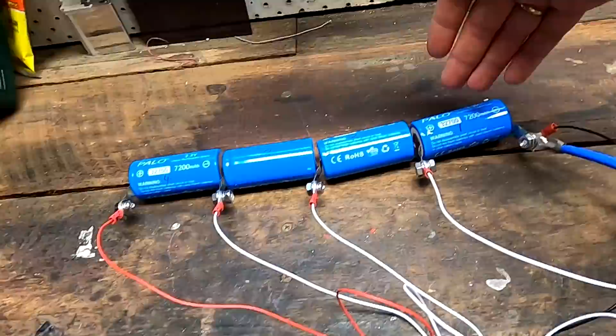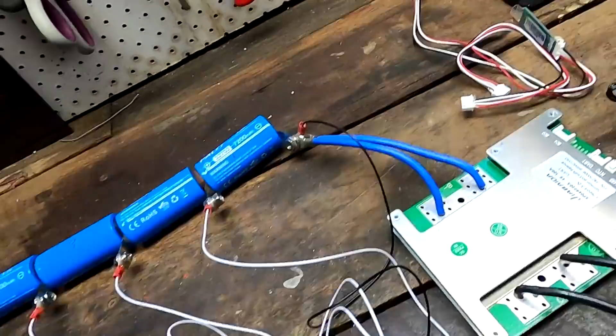In the manual, it says especially to connect the B- cable first. I'm not sure if this is a general rule for BMSs, but I usually forget to connect the B- cable and I hook in all the balance cables and then I wonder why cell number 1 is not reporting correctly. We should stick with what's in the manual, right? We don't want to have any magic smoke here on the bench.